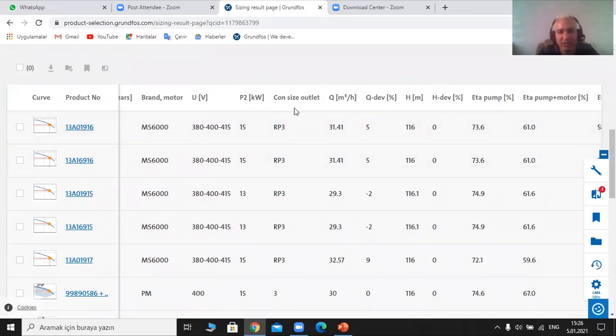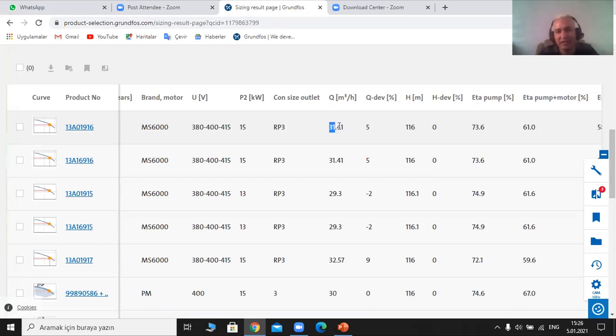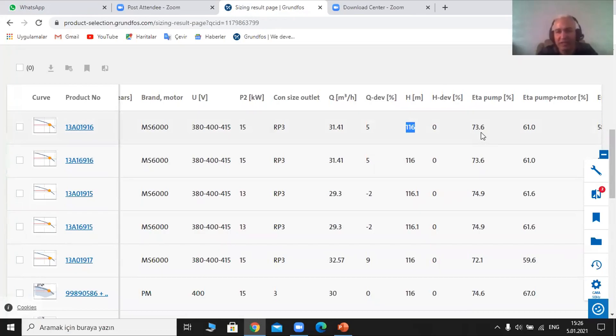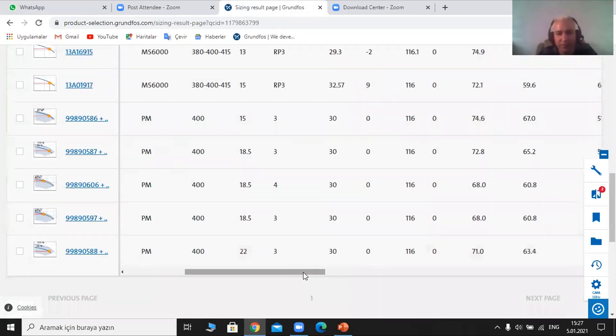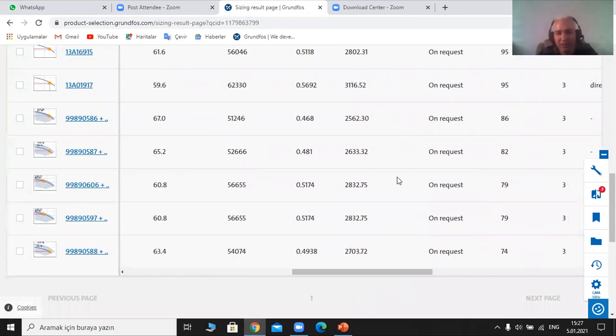Going to the next page, it provides for this pump the outlet, which is RP3 — three inches. The flow rate is 31.41; we asked for 30 but it doesn't provide exactly 30, and the deviation is about 5%. The head is 116 exactly as I asked, so the difference there is zero. The efficiency rate here is 73.6%, and the pump and motor efficiency together is 61%. For submersible pumps, the typical efficiency is between 80 and 85%.